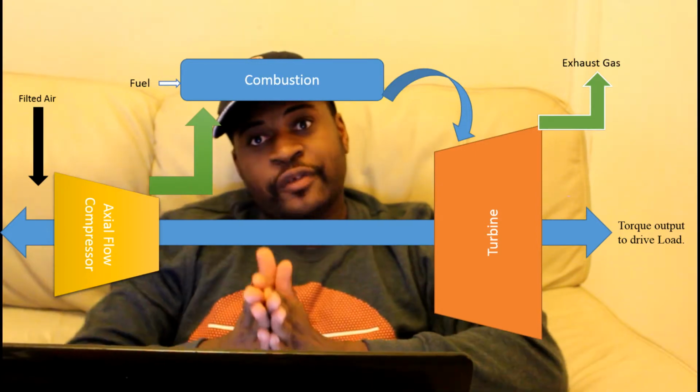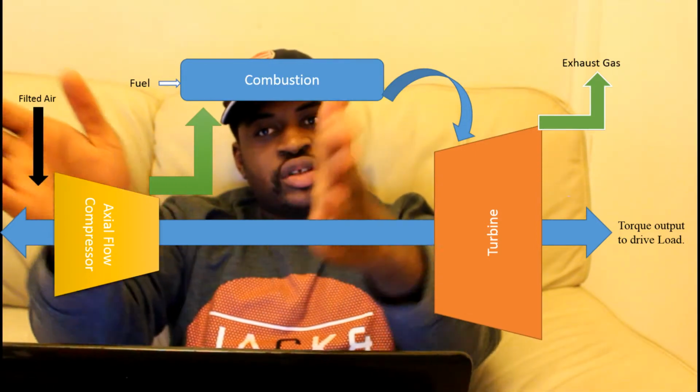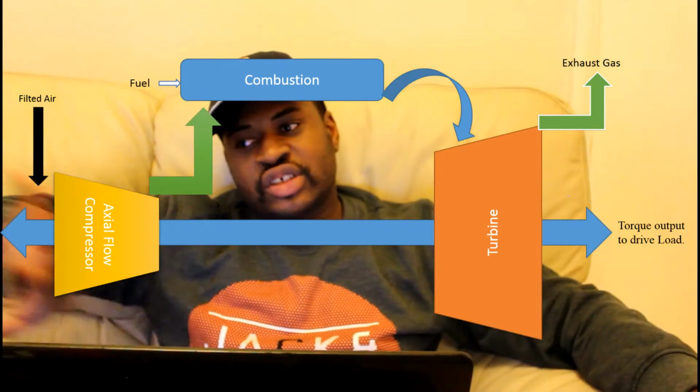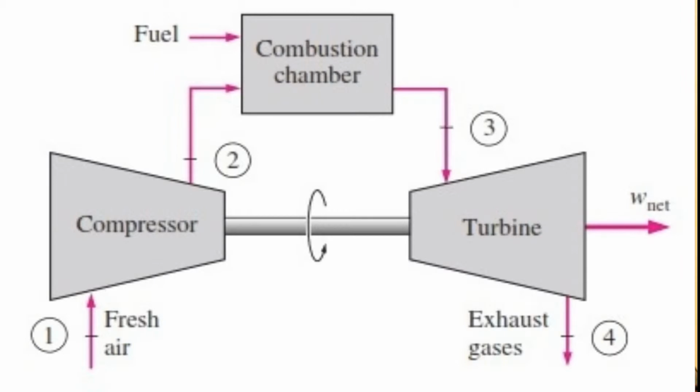As the hot flue gas goes into the turbine, it expands. The turbine expands the gas, so the volume increases and the pressure reduces. The turbine and the compressor work in almost opposite ways, in that the compressor usually starts off large and then goes down, and the turbine starts off small and then goes up bigger. So in the compressor, volume is reducing, and in the turbine, volume is increasing as you go along in each stage, and pressure is reducing. Okay, so that's stage 3.